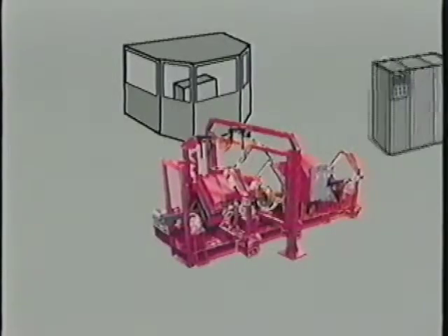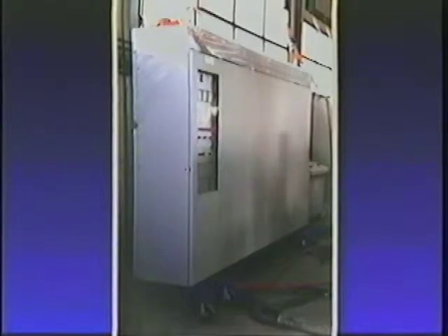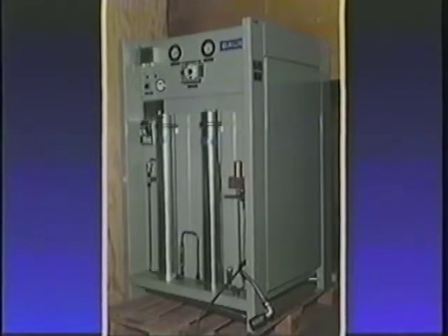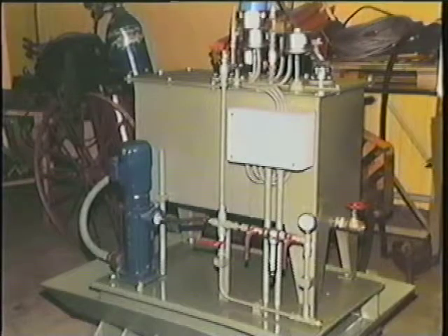The associated high-frequency generator supplies approximately 100 kilowatts at 40 kilohertz. A cooling air compressor supports the sensitive infrared detectors by producing extremely clean and dry air at 200 bar. The moistening system consists of a tank with necessary pumps and filters and supplies water at constant pressure.